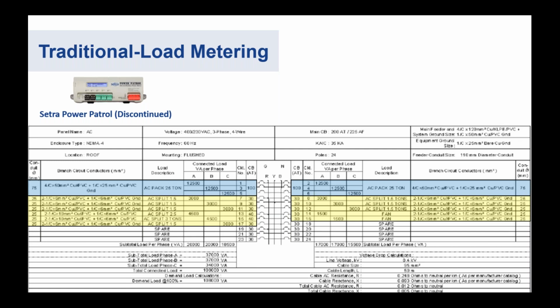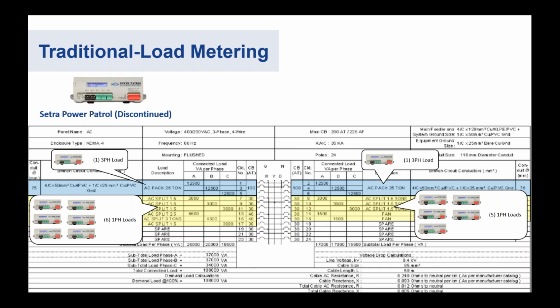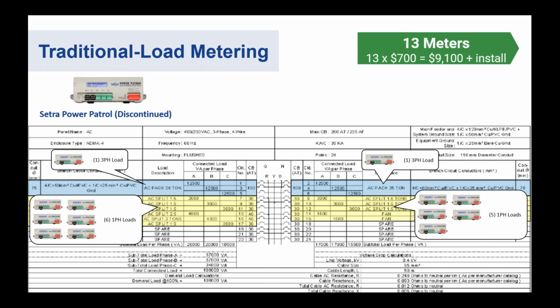When we took a look at this with the customer and added up how many loads, they were going to need 13 Setra Power Patrols in order to solve this problem and get the data and granularity that they wanted. With 13 meters, and with CTs in the meter, it's about $700 a piece. So it's about $9,100 list plus all the install. And for any of the electricians out there, wiring that high voltage is the most dangerous part of the installations, no matter what power meter you're using. So having to do that 13 times becomes pretty costly due to some safety precautions that they may need to take.